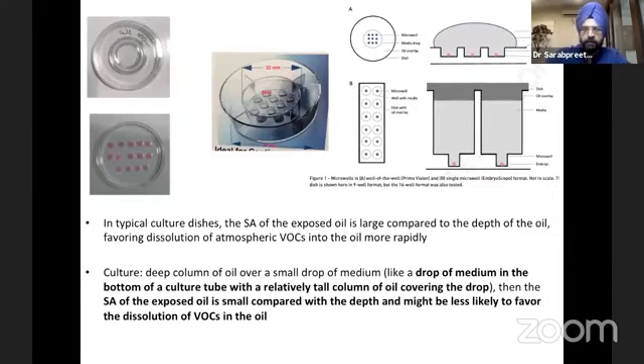But if you look at another kind of dish, the one on your right, I'm not sure whether you can see the mouse. In the typical culture dishes, the surface area of the exposed oil is large compared to the depth of the oil, favoring dissolution of atmospheric VOCs into the oil more rapidly. Look at the dishes on the left. They can lead to dissolution of VOCs into the oil, whereas on the dishes on the right, there's a deep column of oil over a small drop of media, like a drop of medium in the bottom of a culture tube, with a relatively tall column of oil covering the drop. Then the surface area of the exposed oil is small compared with the depth, and this is less likely to favor the dissolution of VOCs. So in these kinds of dishes, there is less chance of dissolution of VOCs. So layer the dishes with the maximum amount of oil you can.